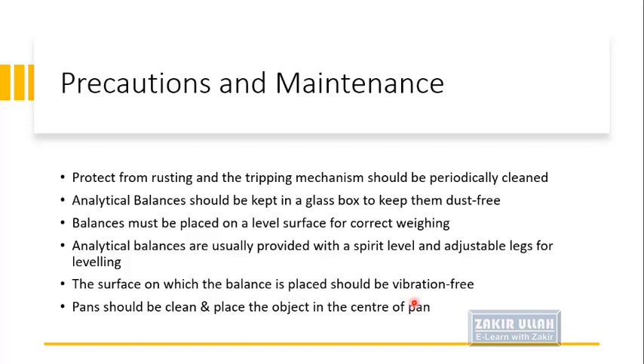Regarding precautions and maintenance: protect all balances from rusting and tripping mechanisms, and clean them periodically. Analytical balances should be kept in a glass case to keep them dust-free. Balances must be placed on a level surface so that weighing is correct and unbiased. Analytical balances are provided with a spirit level and adjustable legs for leveling, and the surface should be vibration-free.